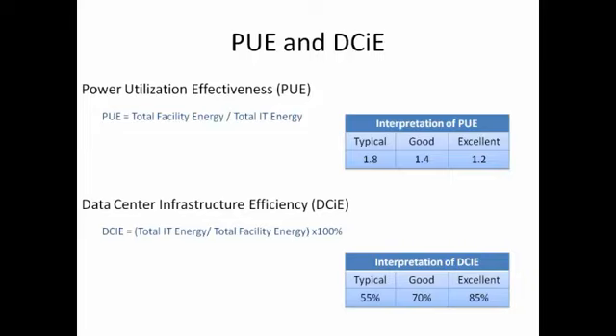DCIE is the same. It's just inversed times 100%. So if you get near 100%, you're great. 55, not so good. Same thing, PUE 1.2. You want that to go down. So 1.0 would mean that there is no energy going to the cooling system at all. You've got the windows open. 1.2 means, of course, that you're spending a little bit of energy on everything other than IT, etc.